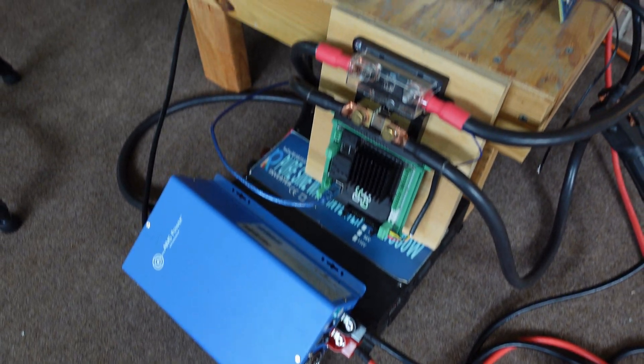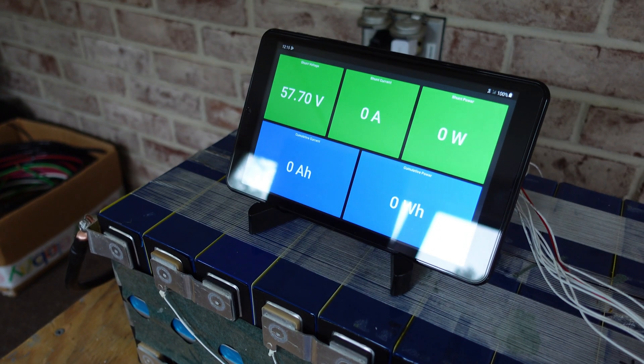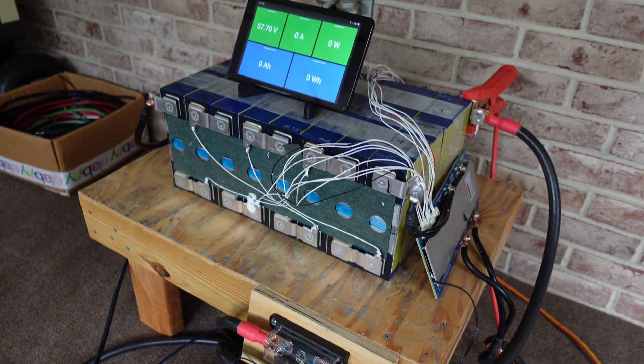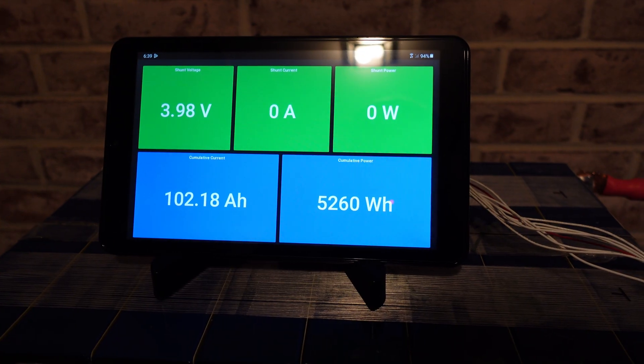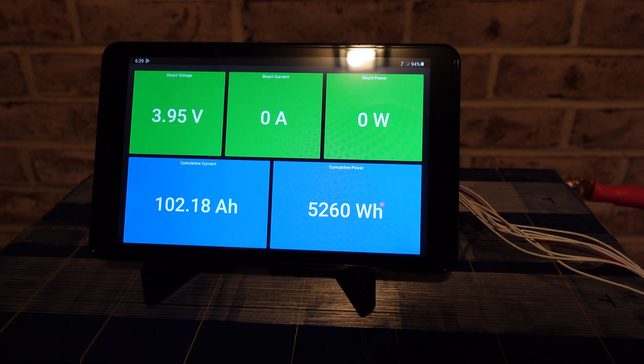We've completed the second charge cycle, resting at 57.70 volts, and this has been sitting on the charger overnight. So now we're ready for the second capacity test. Test number two finished at 102.18 amp hours.